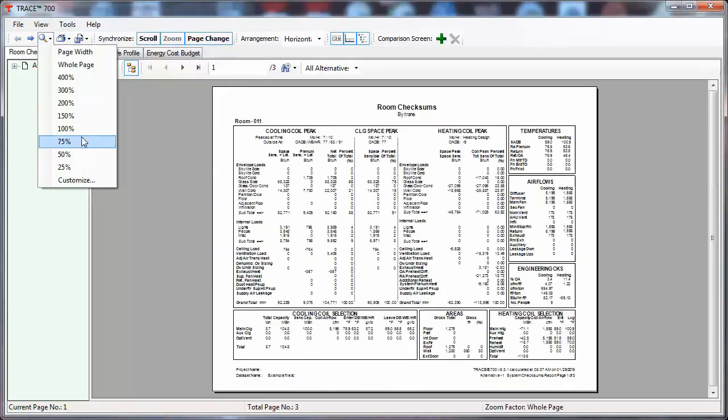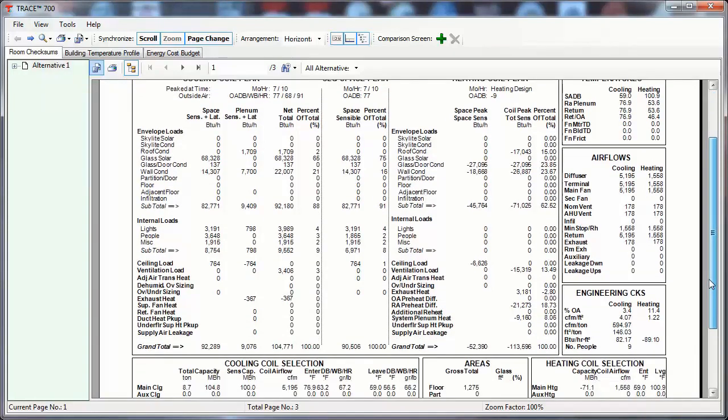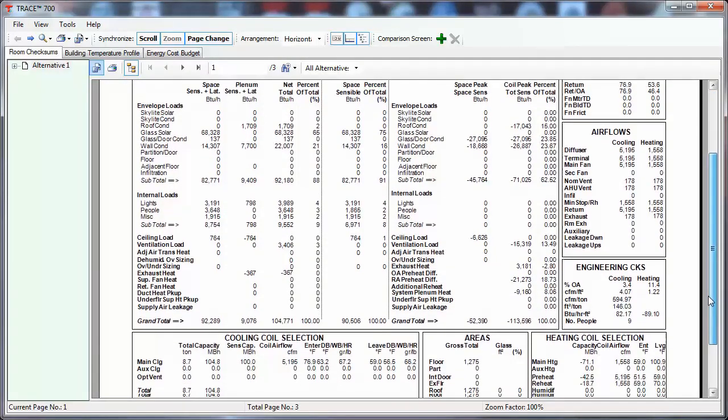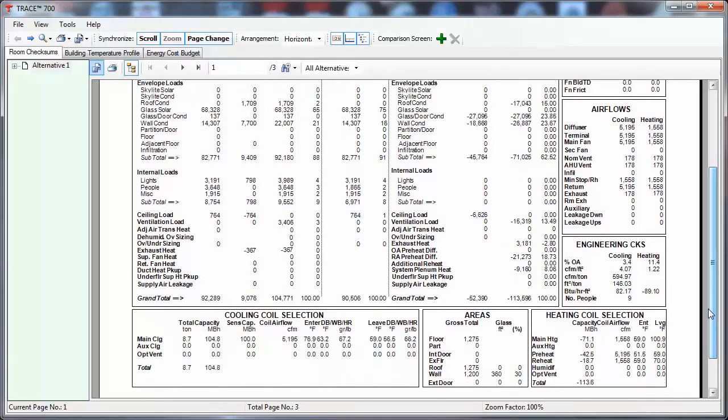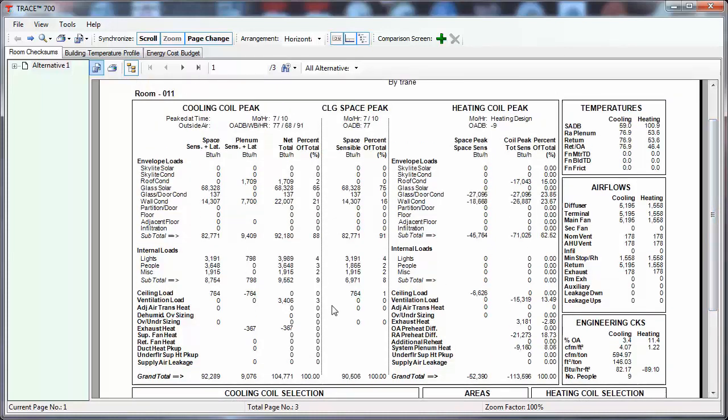Next, if you find a room that is giving you plenty of unmet hours, look at the Room Checksums Report. Here you are going to look at two different outputs. The first output is the Supply Air Dry Bulb. The second output is the Main Fan Air Flow. The reason we want to look at these two parameters is because if you have a room that has quite a bit of unmet hours, it is normally because there is a low cooling or low heating coil capacity for the space and/or system. The reason for this low capacity could be that the space load during design, which is what the Checksums show, is very minimal. With a small load, either the Supply Air Dry Bulb will result in a very small delta T, or your Main Fan CFM will be very low compared to a typical diffuser CFM.